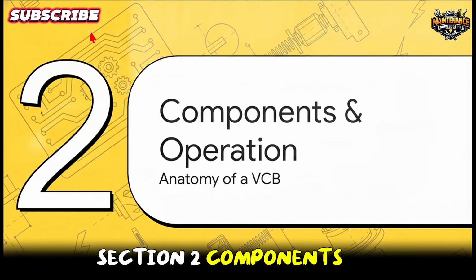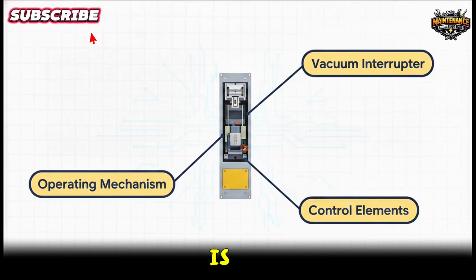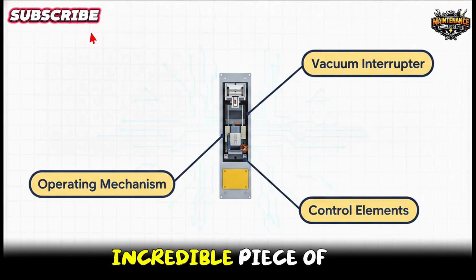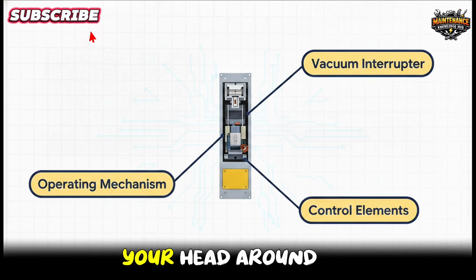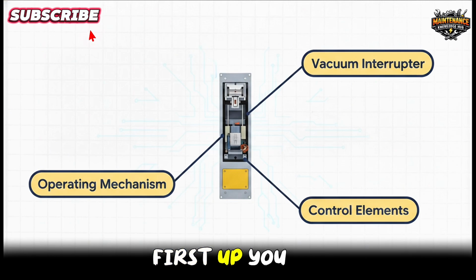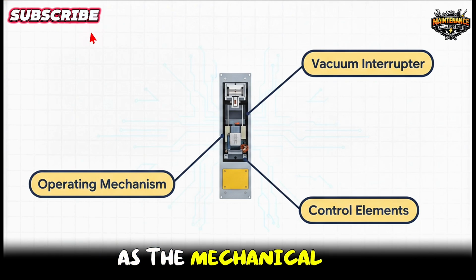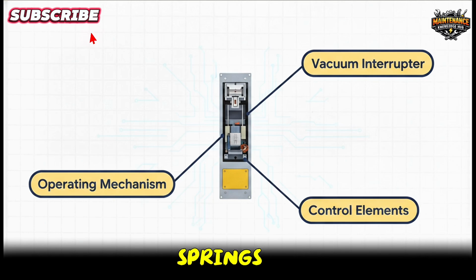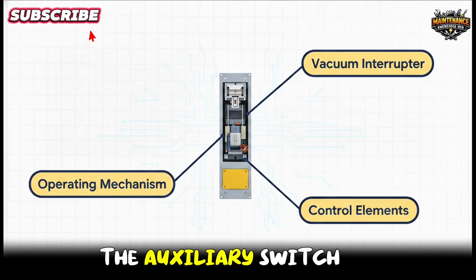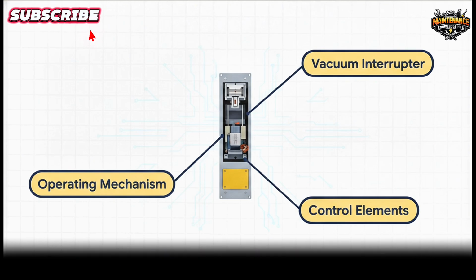Section 2. Components and operation. Now that we know what it is, let's pop the hood and look at the anatomy of this incredible piece of engineering. To really wrap your head around a VCB, you can logically chunk its main components into 3 distinct parts. First up, you have the vacuum interrupter itself, which houses the fixed and moving contacts. Second is the operating mechanism. Think of this as the mechanical muscle. This includes your closing and opening springs, plus the main shaft. And third, we have the control elements. This is the brain of the operation, featuring the trip and closing coils, the auxiliary switch, and your safety interlocking mechanisms. Every single one of these has to work together perfectly as a unified system.